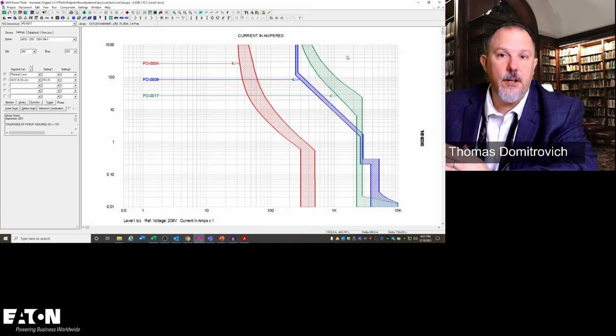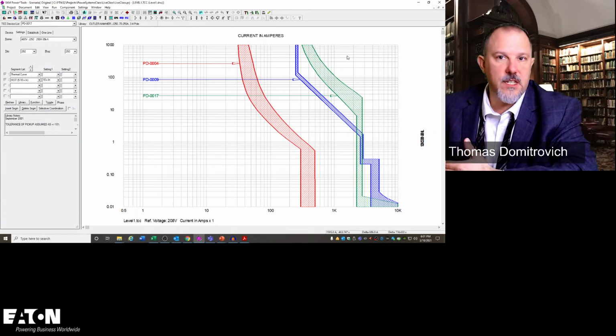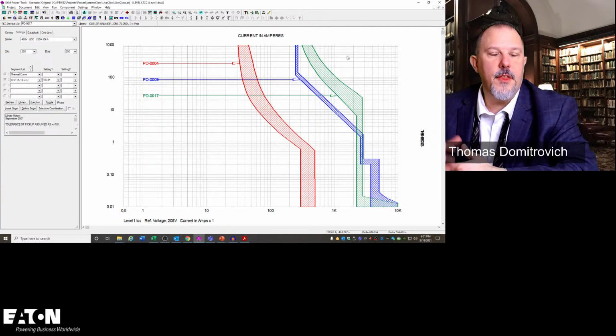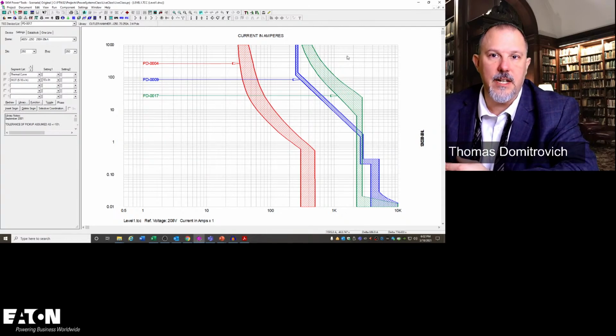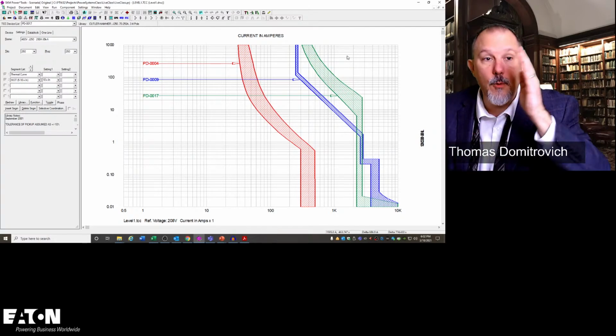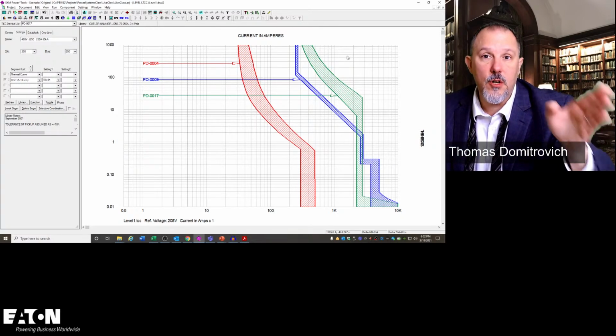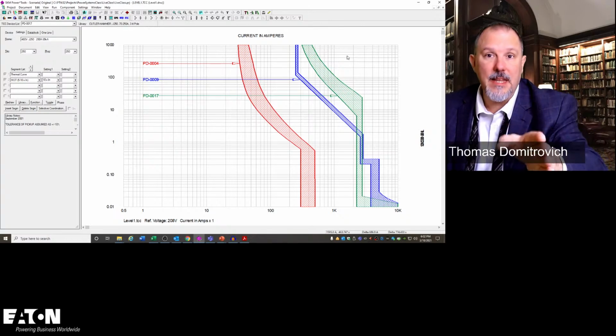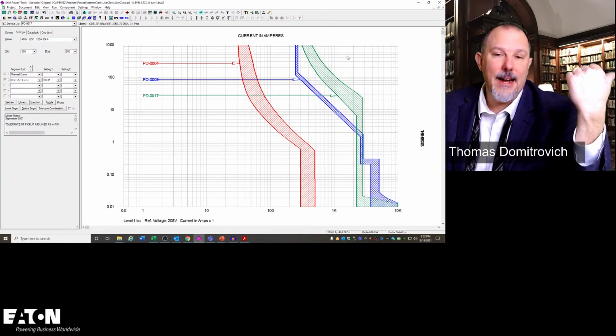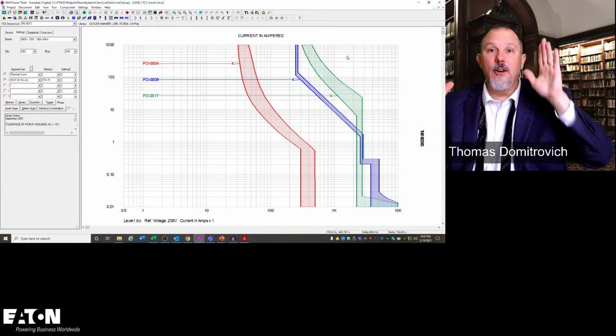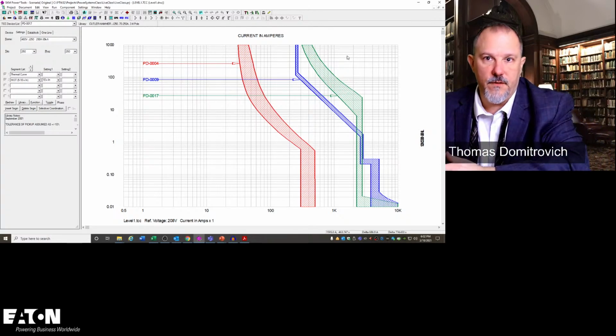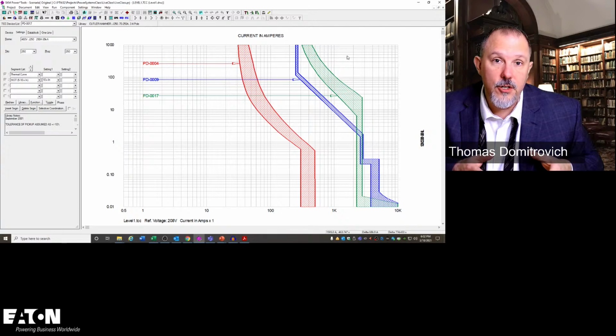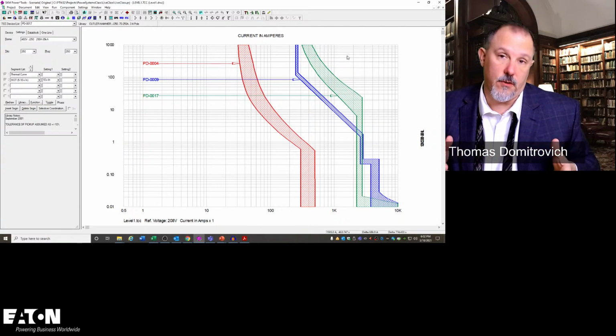They would tell you the percentage values, and I would say, okay, based upon IEEE 242 or 141, whichever book I was using, they say the most common fault is an arcing ground fault, and based upon their references, it's 60% or 70%, whatever percentage, of the bolted fault current, and I would plot that number. If that number was lower than the instantaneous region of the upstream device and higher than the instantaneous of the downstream device, I'd say, okay, look, you don't selectively coordinate to a three-phase bolted fault current, but you do coordinate to the arcing ground fault current, or the ground fault current.